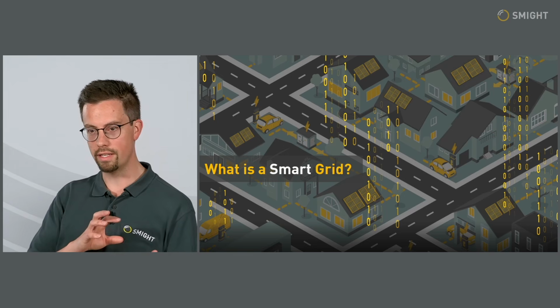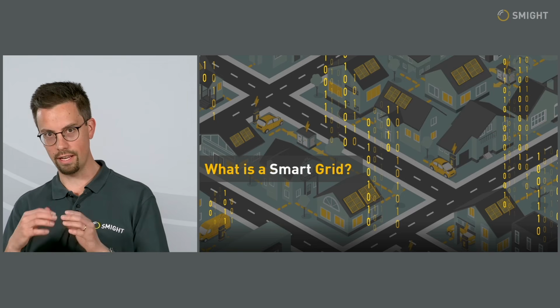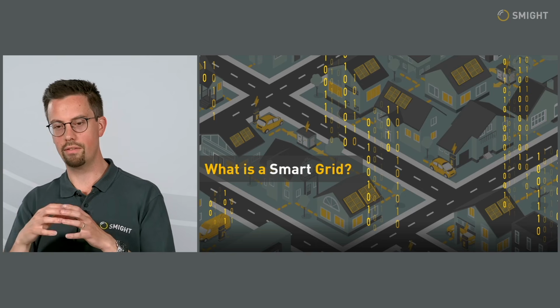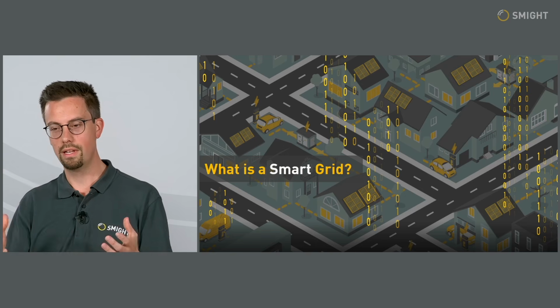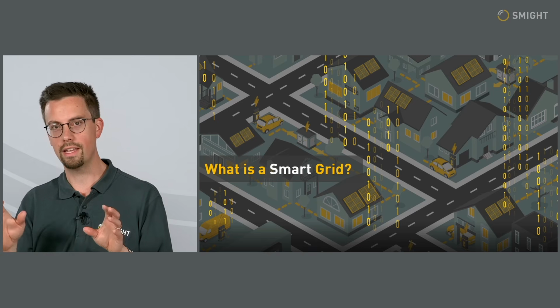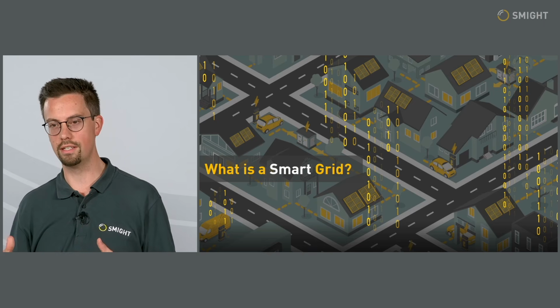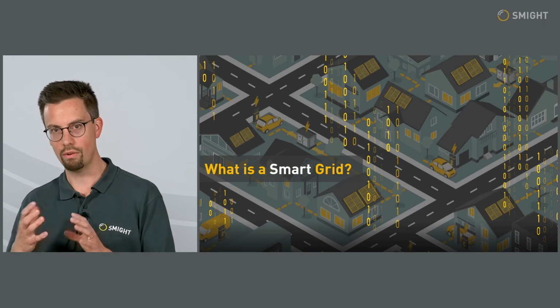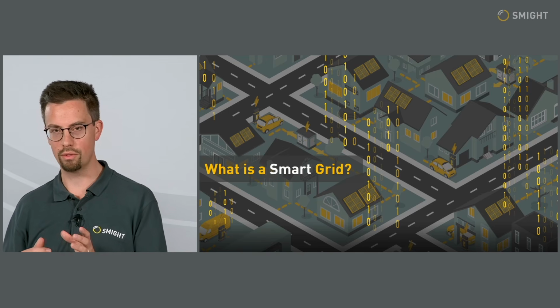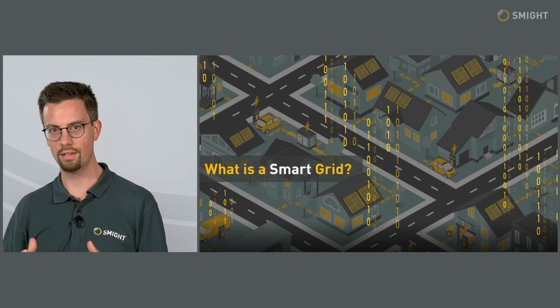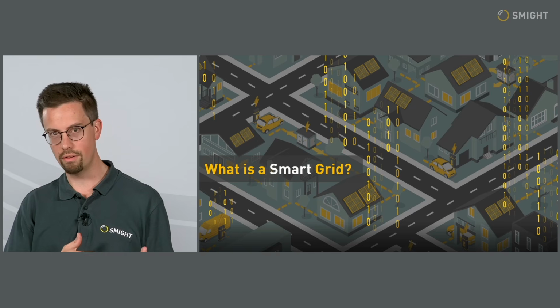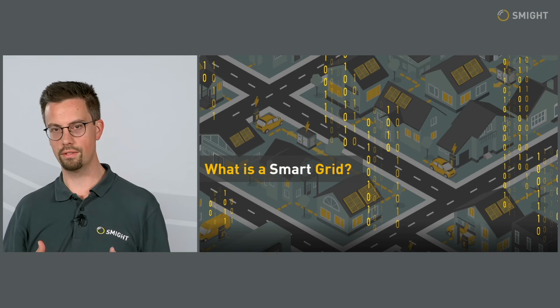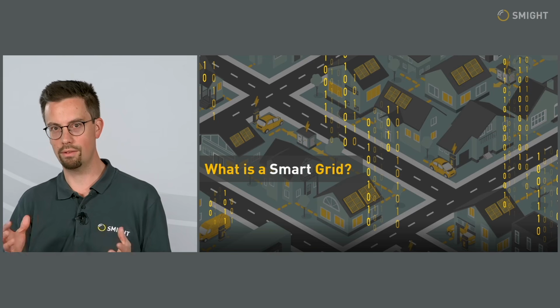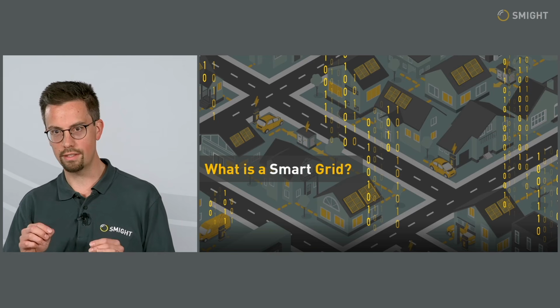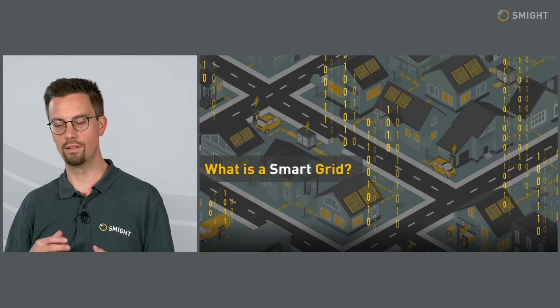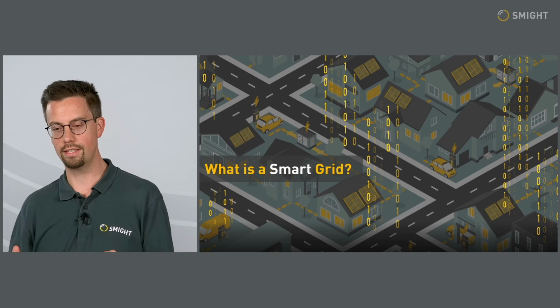So we've got the self-aware side, but then there's the control side. If we take the higher voltage levels, you have a control system, you have people who can oversee that, because the numbers there are so much easier to deal with. As a comparison, a typical relatively large network might have somewhere between 100 and 200 primary substations, whereas that same network at the low voltage level would have tens of thousands of secondary substations. You simply cannot manage that number of points, loads, and the dynamic that comes with that through people sitting in a control room.